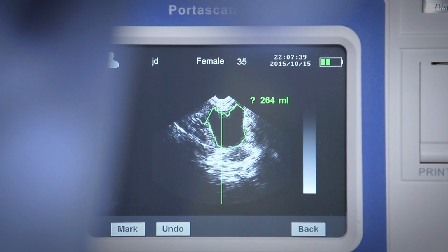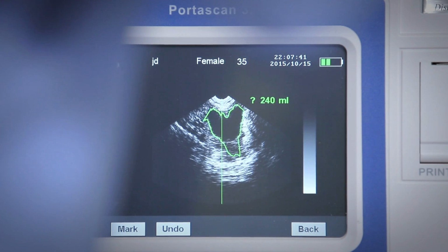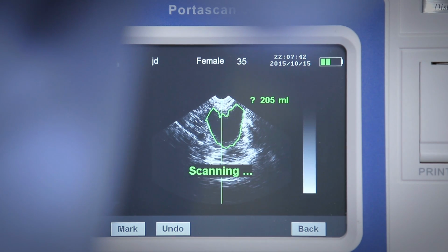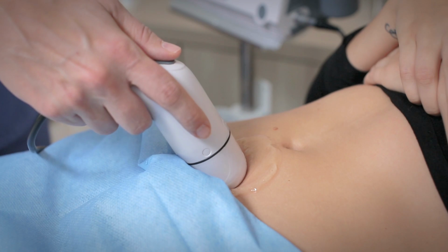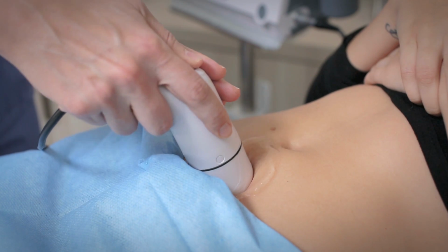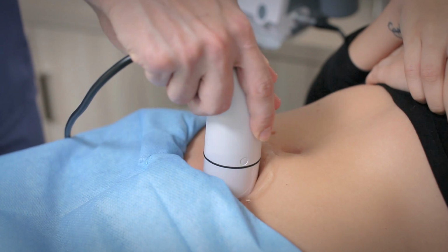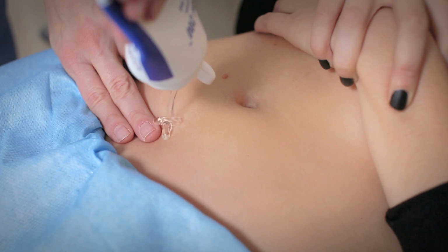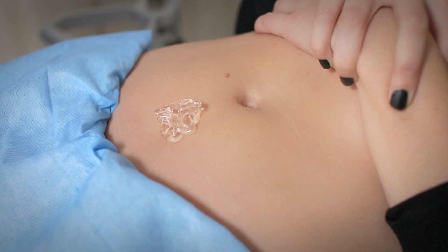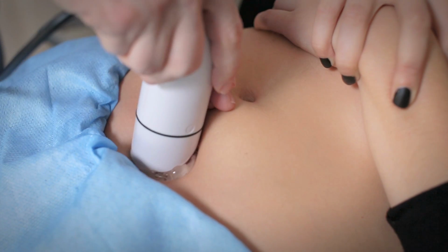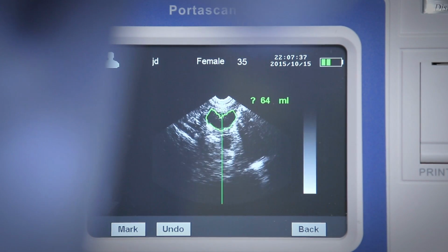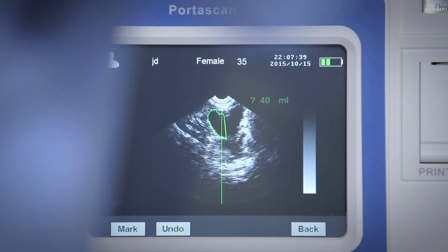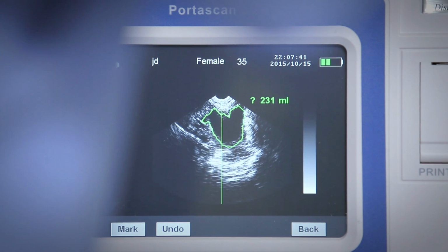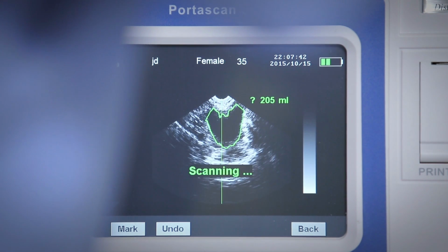The bladder silhouette should appear in the center of the crosshairs. If it does not, you may need to repeat the scan with the probe at a different angle. Adjust the angle to move the bladder image towards the center. You may find that applying more ultrasound gel, applying more pressure, or adjusting the gain is necessary to improve the scan. Once you obtain the first scan, you can perform a second scan to validate that accuracy is within 10%.